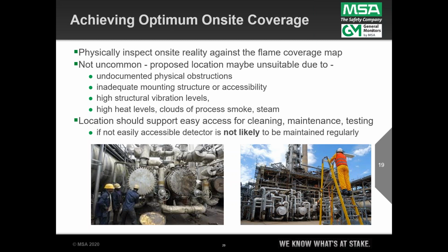This map, it's amazing what we can do now. But the bottom line is, with some locations, when you get to site, if you see that there's a piece of steel in front of it, well, that's not going to work. And maybe the map, the draftsperson, the person running the program, didn't know that was there. That's the reality. These are complex sites, and these photos represent that. It's not unusual to see undocumented physical obstructions in the way of the flame detector, and the same with the gas detectors as well.